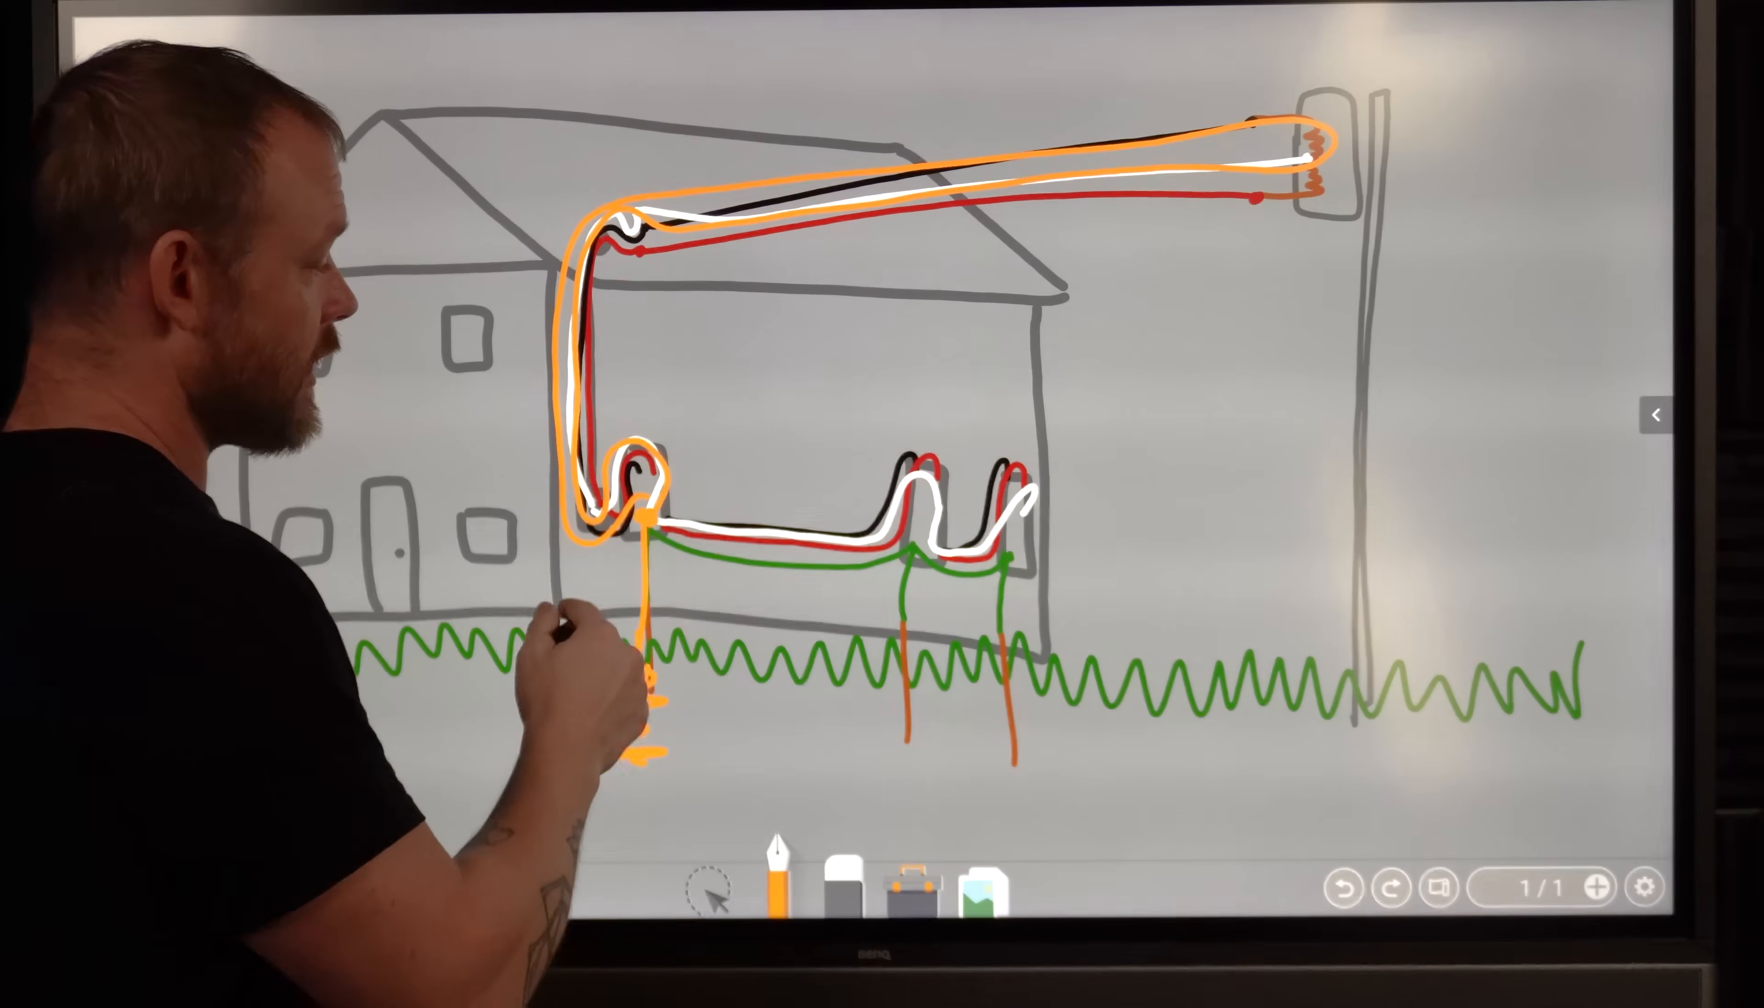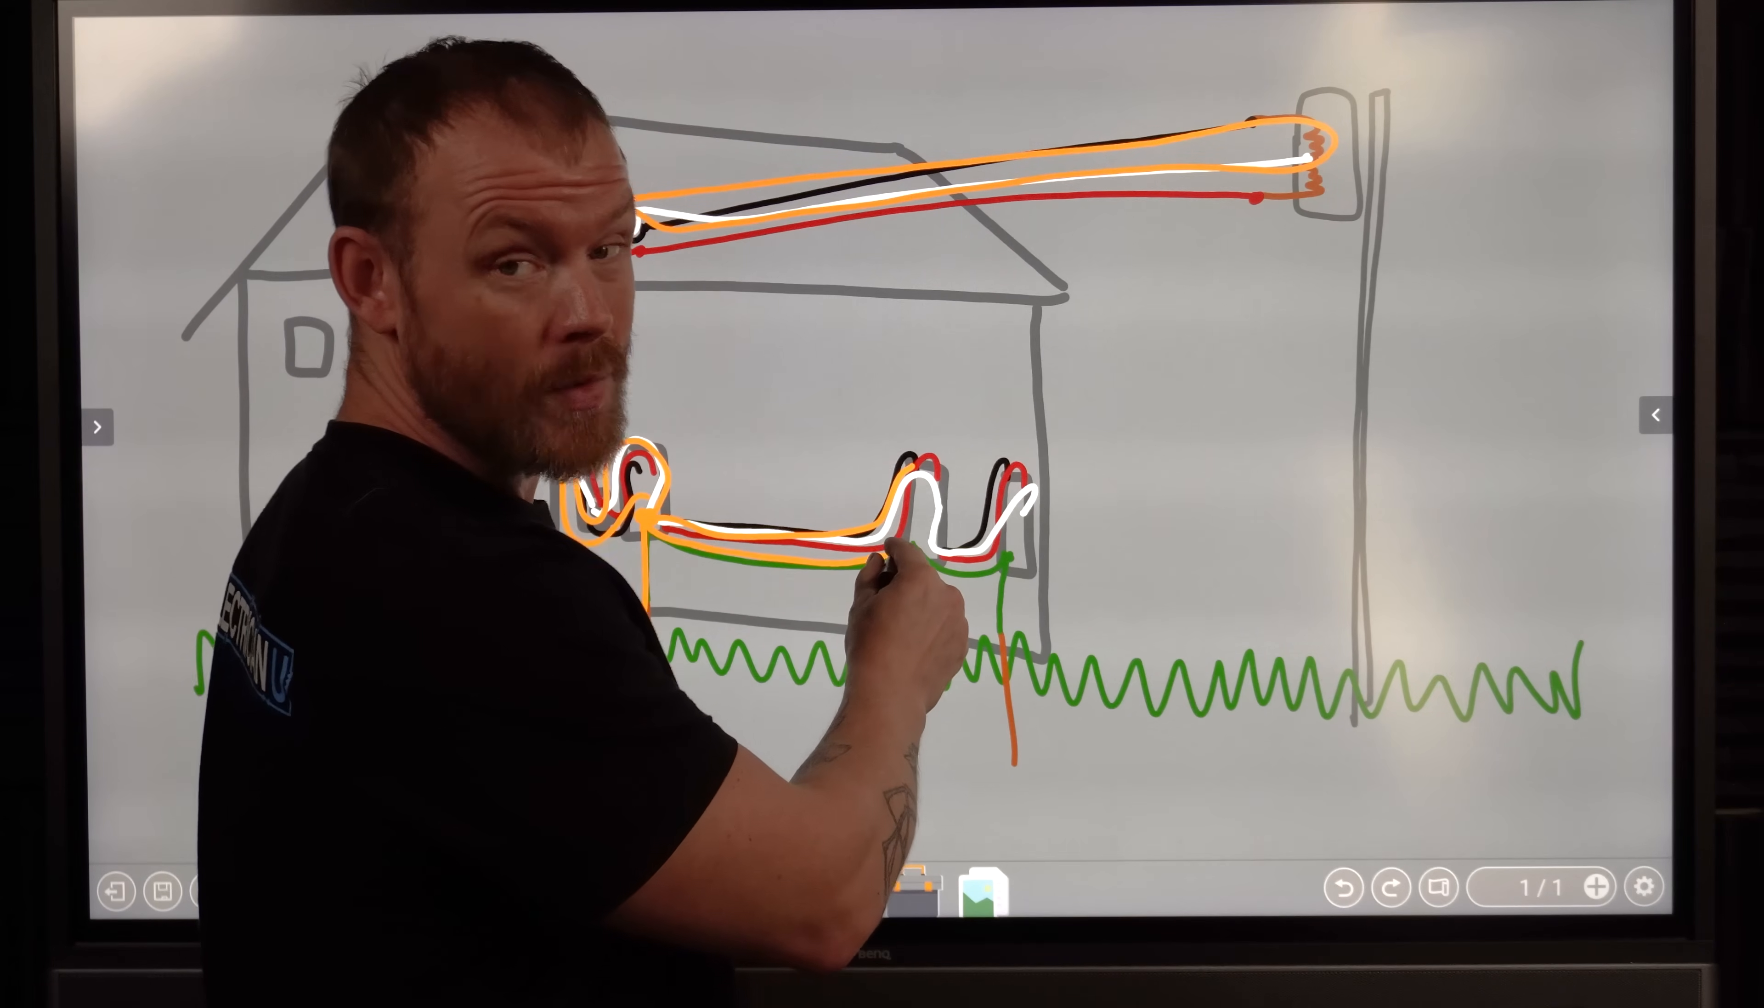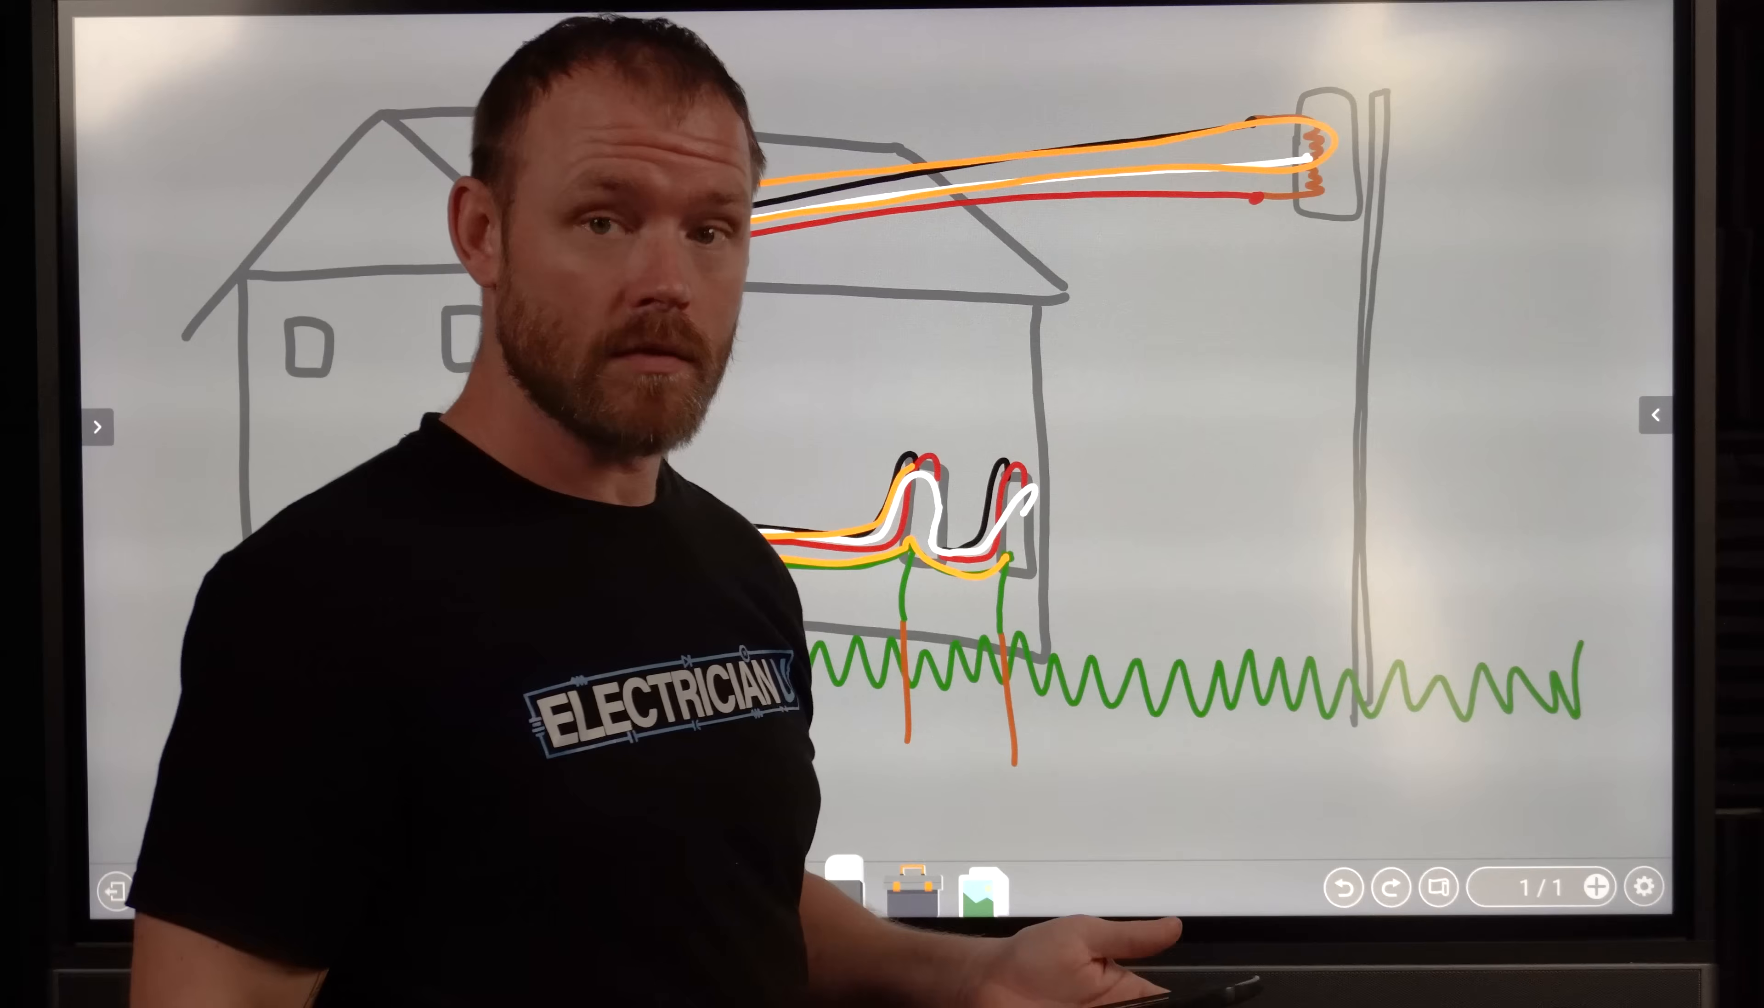But I was talking about how we have different sub-panels, right? You can run more circuits over and you just have to make sure you run an equipment grounding conductor, not a grounding electrode conductor, an equipment grounding conductor to each one of the panels. But he was asking, what about having a separate ground rod for each panel? Can you do that?